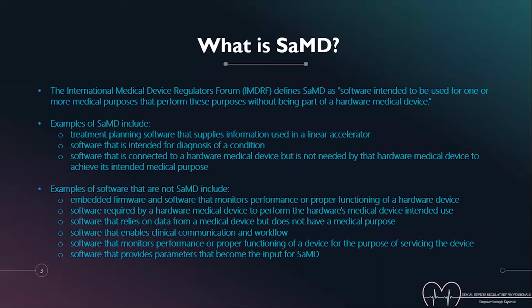I think it becomes easier when you also think about software which cannot be called SaMD. These include software used as embedded firmware to monitor the performance of a device. If you think about infusion pumps used on patients, these infusion pumps are medical devices, but the software that is making them function won't qualify as software as a medical device. Similarly, software required by a hardware medical device to perform its intended use is not going to be classified as SaMD. Then there is software that relies on data from a medical device but does not serve a medical purpose.